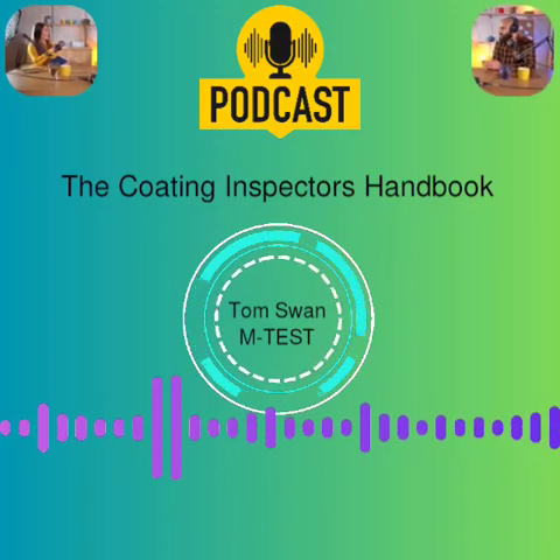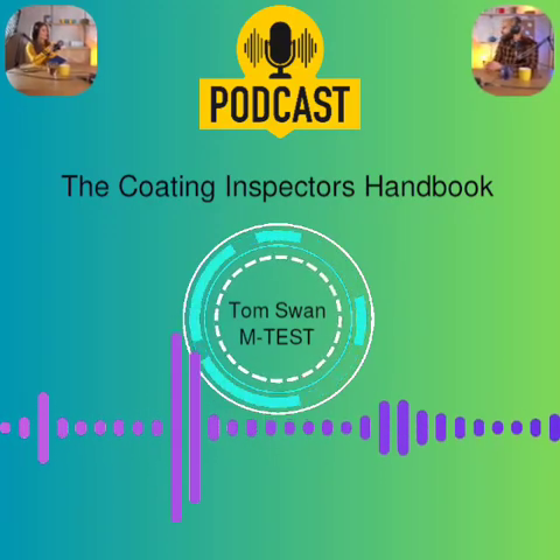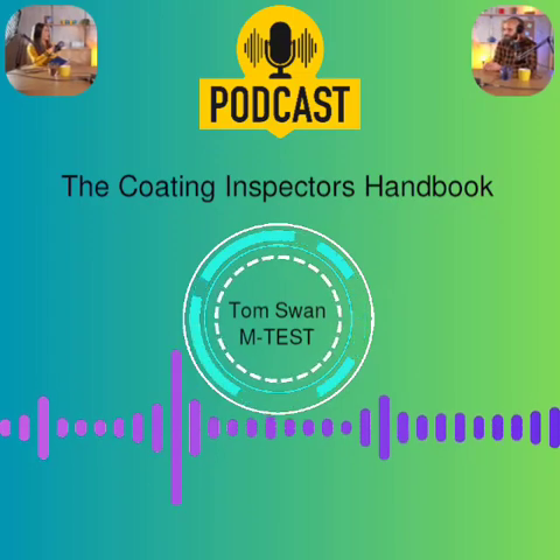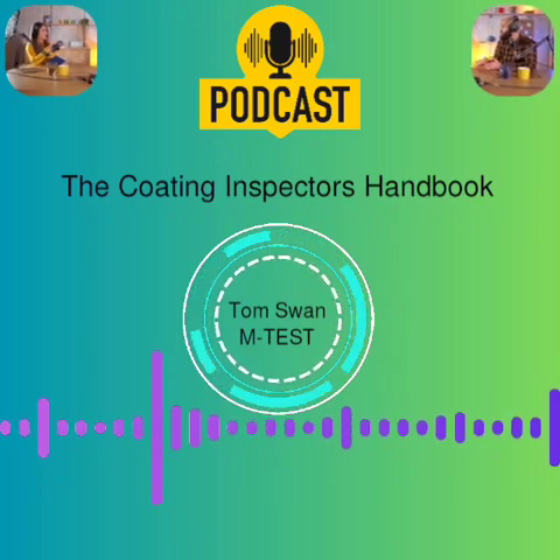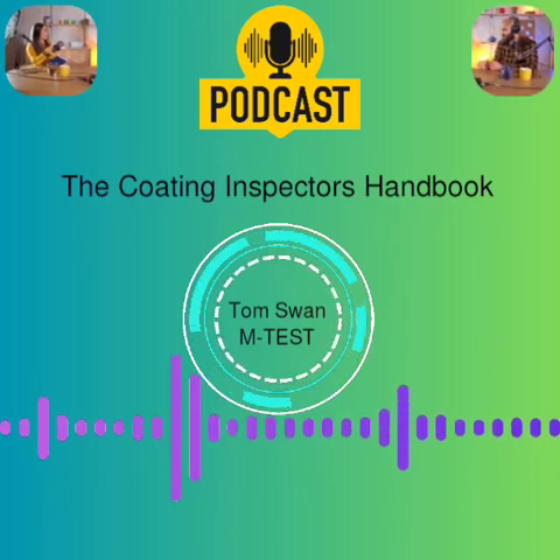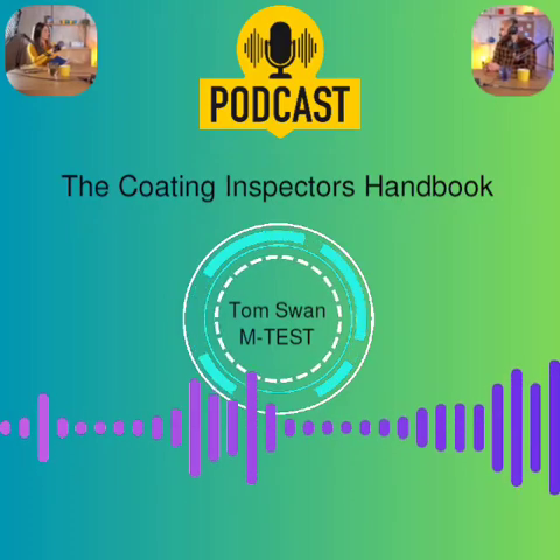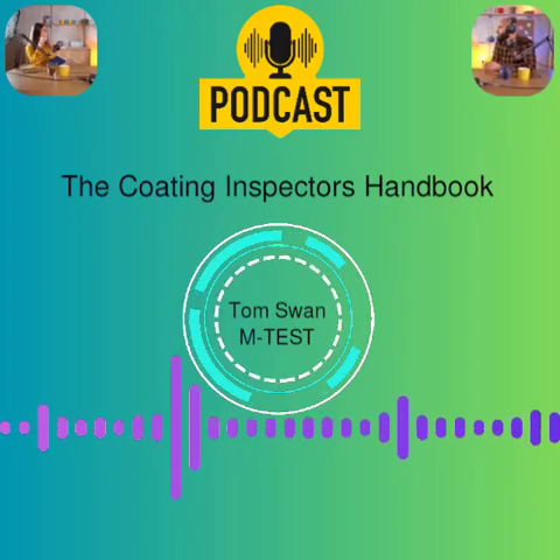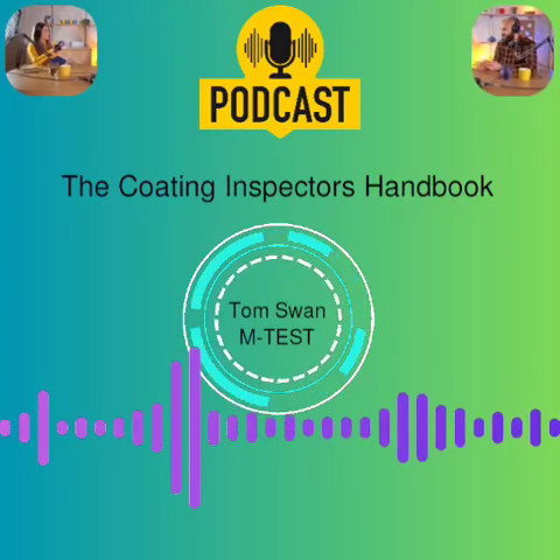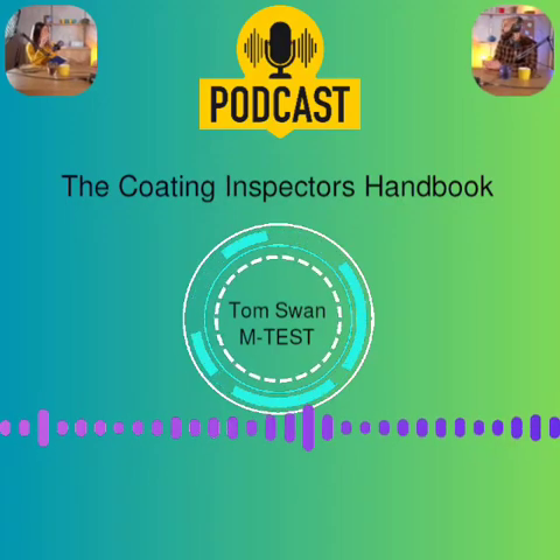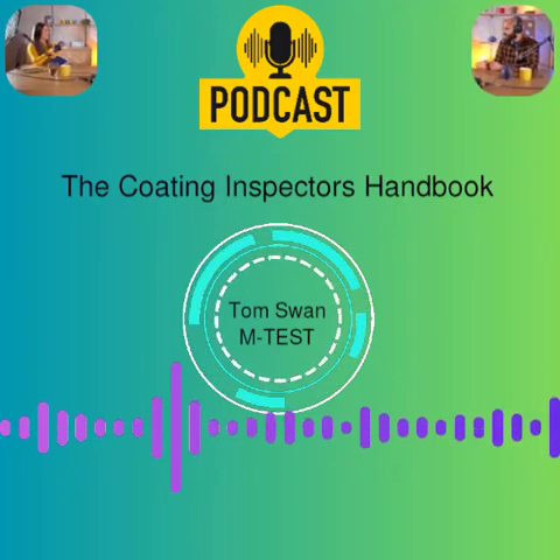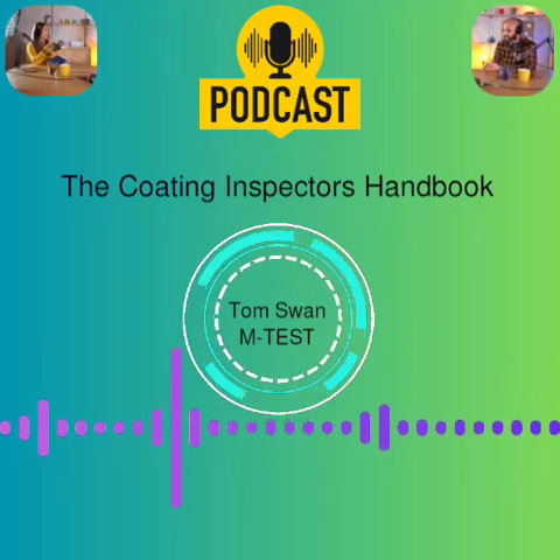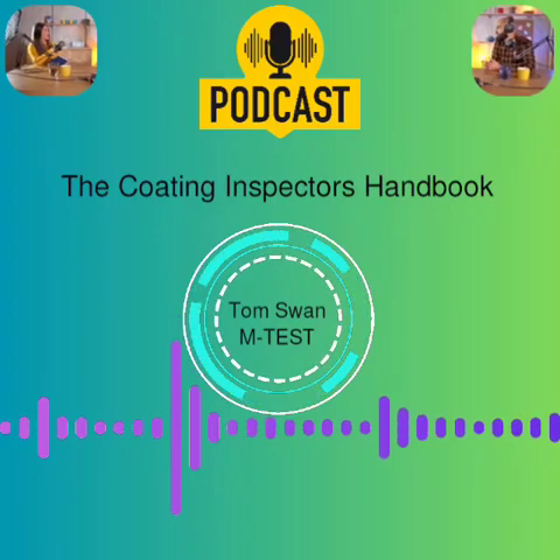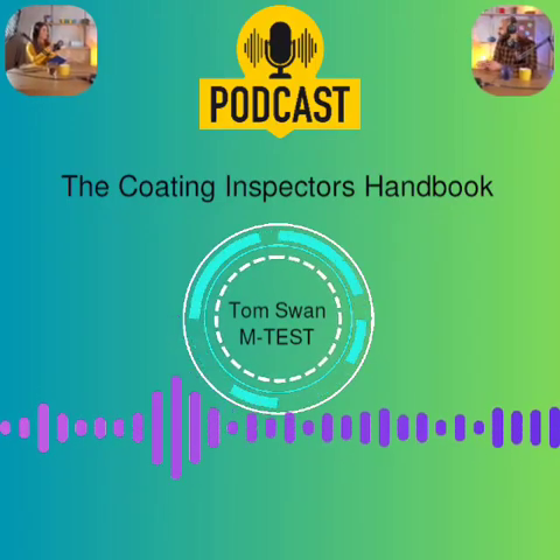Right, unless the air is totally saturated, 100% humidity. The difference between dry bulb and wet bulb tells you how much moisture is in the air. Big difference means dry air, lots of evaporation. Small difference means humid air, less evaporation. And dew point. That's the temperature where the air becomes saturated and moisture will start to condense out onto surfaces. If your steel surface is at or below the dew point, you'll get condensation, invisible moisture.